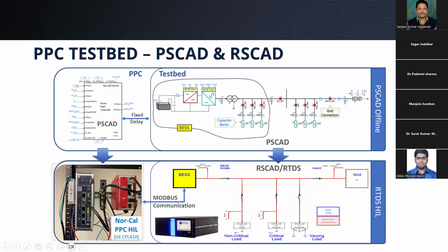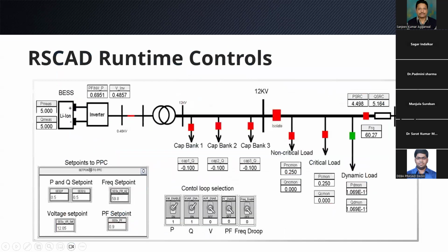So what we'll do here is create this model. You will interface the physical PPC with the simulated grid, and perform the same test which you performed on the PSCAD model, and compare the responses, whether they are similar or not. If the responses are different, it means the model you created in PSCAD may not be the correct representation of the actual device. RSCAD has an interface called the runtime interface, where you can see the output, change parameters, and change control inputs.